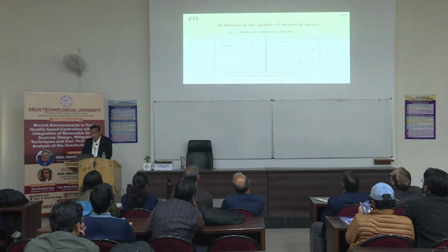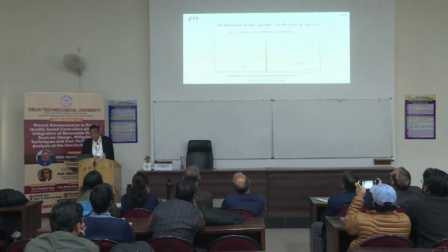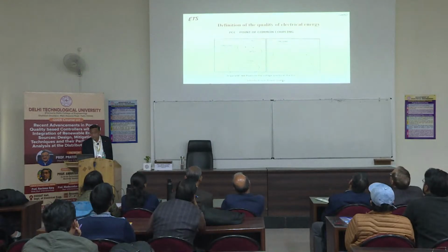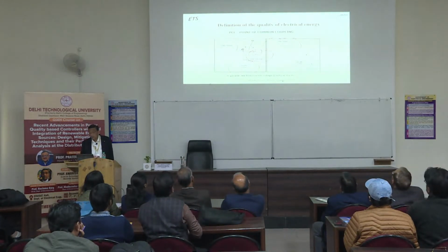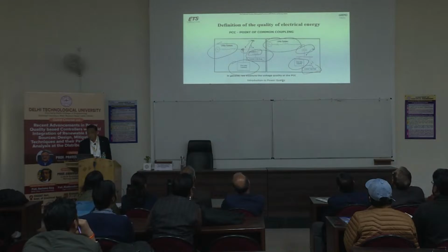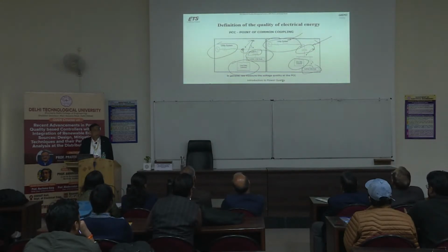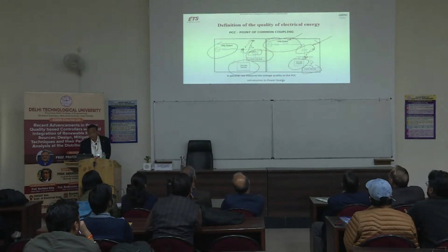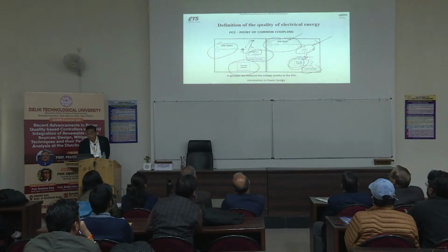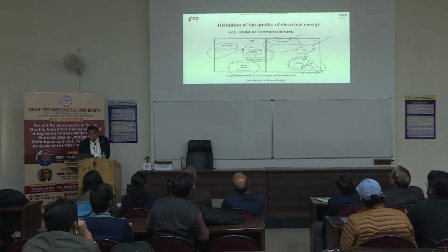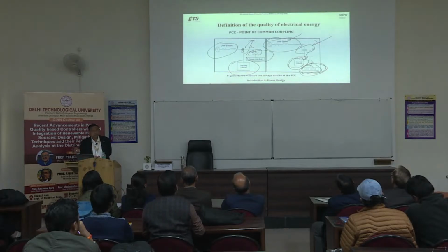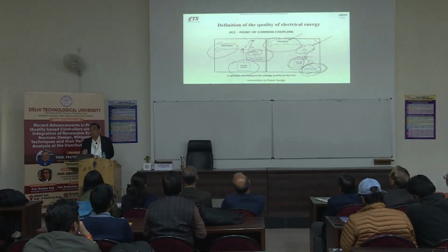So as you can see, some example of PCC, point of common coupling. This is the utility system, supply system, and here is one customer, suppose under study, and this is the transformer of the customer, and there are other customers here. So basically you are saying here, this is the point of common coupling. But in this example, you can see this is the utility system and other customers, and this transformer is perhaps provided by the utility company, and so PCC is here basically. Point of common coupling where many customers are connected. So if one customer is creating a problem, it will be reflected on the PCC, and the other customers will also get affected.